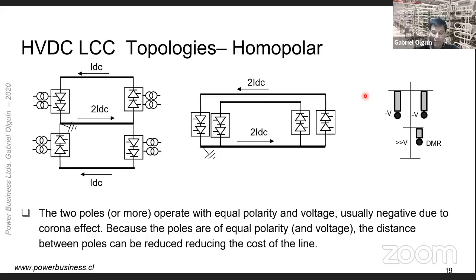Another topology is the so-called homopolar HVDC. In a homopolar HVDC link, the two poles or more operate with equal voltage polarity, usually negative to mitigate the corona effect. Because the poles are at equal polarity, the distance between the poles is less than in the case of two poles at different polarity, a case we will review next, thus reducing the cost of the transmission line. The return current, however, needs to be rated for the sum of the current in both poles. To my knowledge, there is no commercial implementation of this topology.